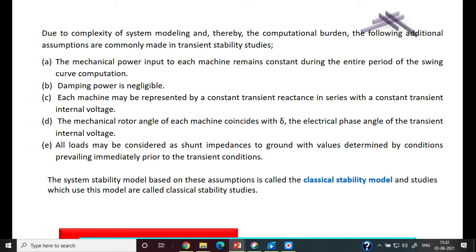The additional assumptions are: the mechanical power input to the machine remains constant during the entire period of swing curve computation; damping power is negligible; each machine may be represented by a constant transient reactance in series with a constant transient internal voltage, that is the voltage behind the transient reactance; and the mechanical rotor angle of each machine coincides with the electrical phase angle of the transient internal voltage.